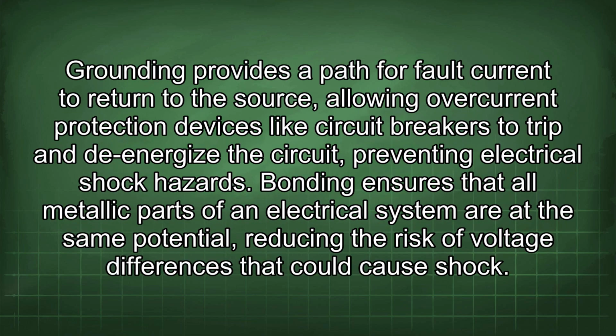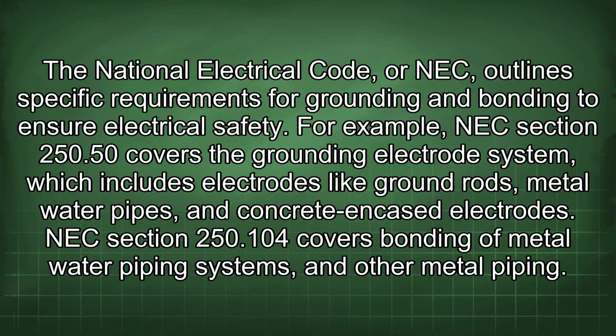Grounding provides a path for fault current to return to the source, allowing overcurrent protection devices like circuit breakers to trip and de-energize the circuit, preventing electrical shock hazards. Bonding ensures that all metallic parts of an electrical system are at the same potential, reducing the risk of voltage differences that could cause shock. The National Electrical Code, or NEC, outlines specific requirements for grounding and bonding to ensure electrical safety.